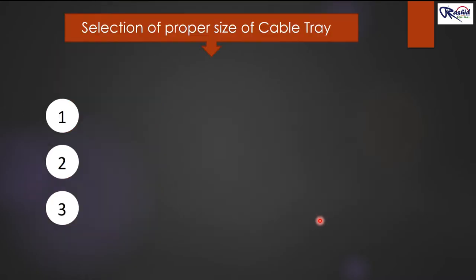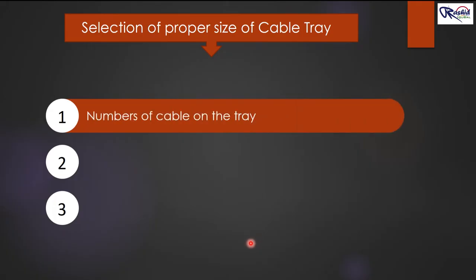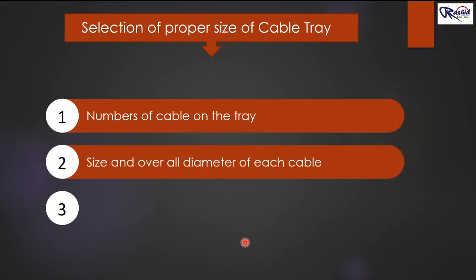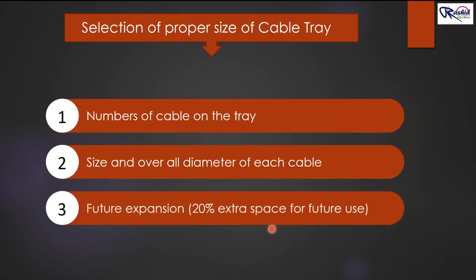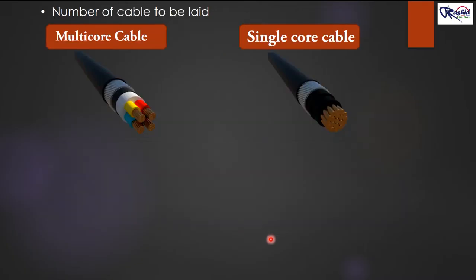Now I am going to calculate the proper size of tray. First, we need to know the total number of cables to be laid in the tray. Second, the size and overall diameter of each cable. Once we calculate the size of cable tray, we will add 20 percent extra space provision for future use. Today we will learn cable tray size calculation for multi-core cable and single core cable.